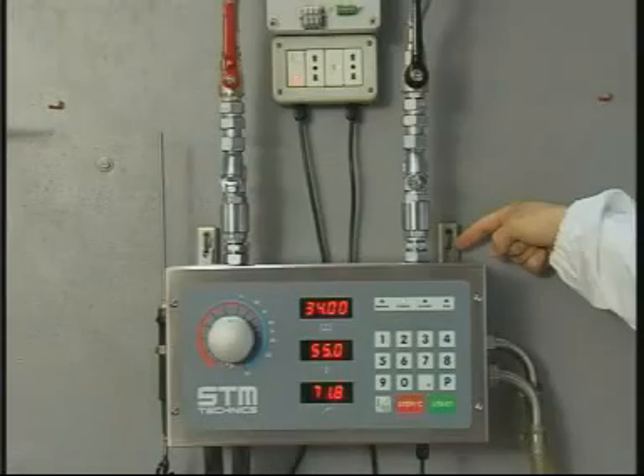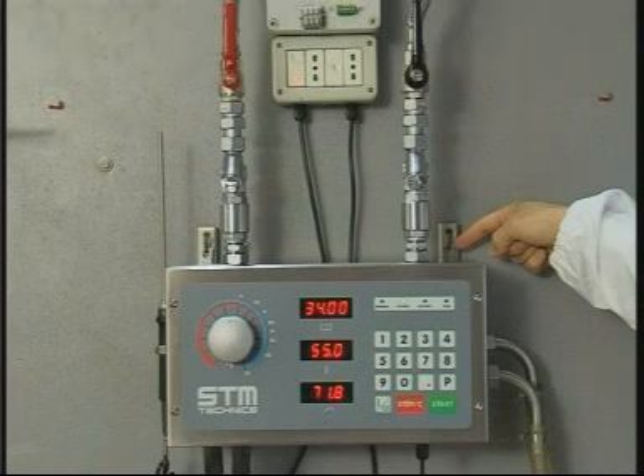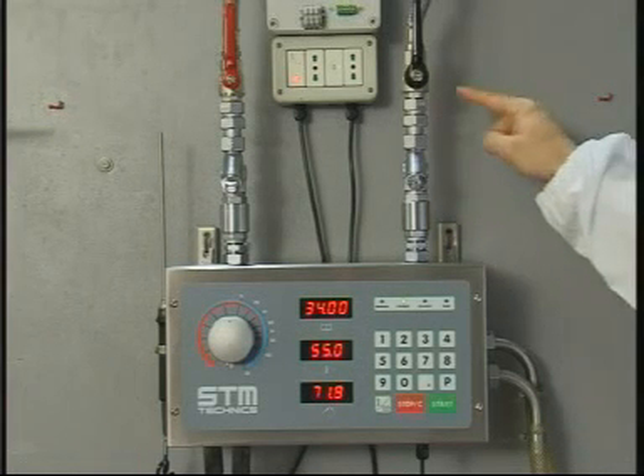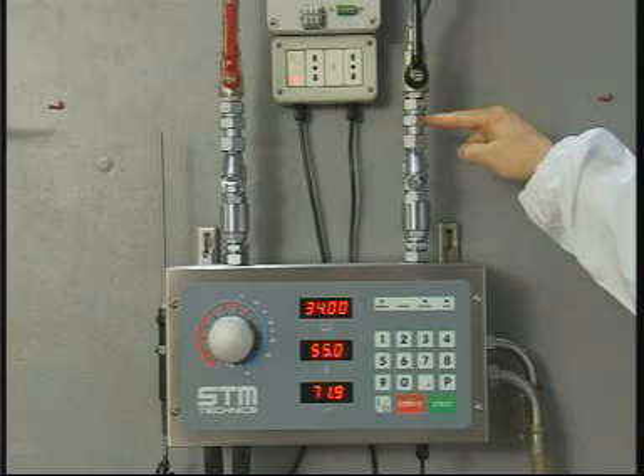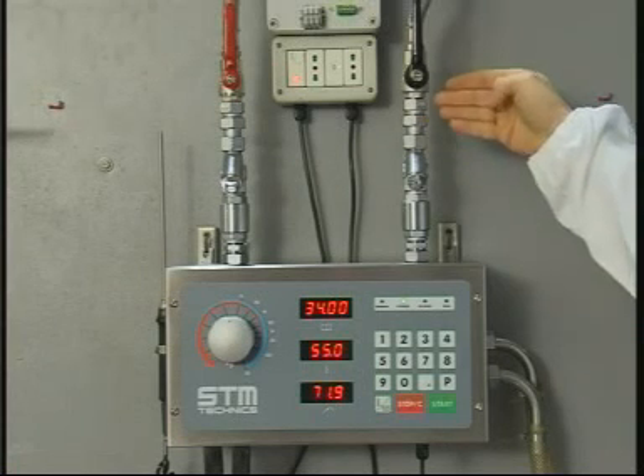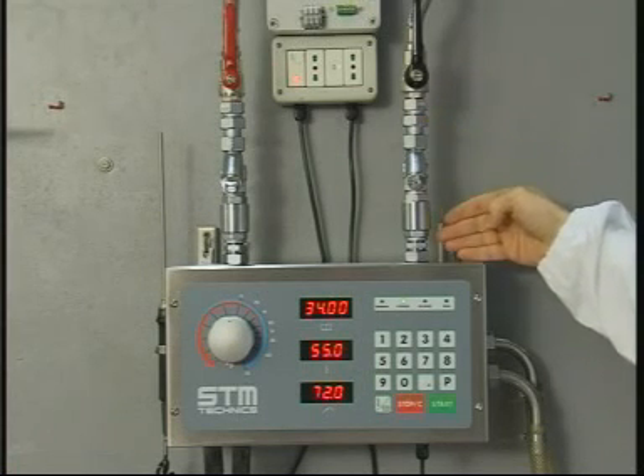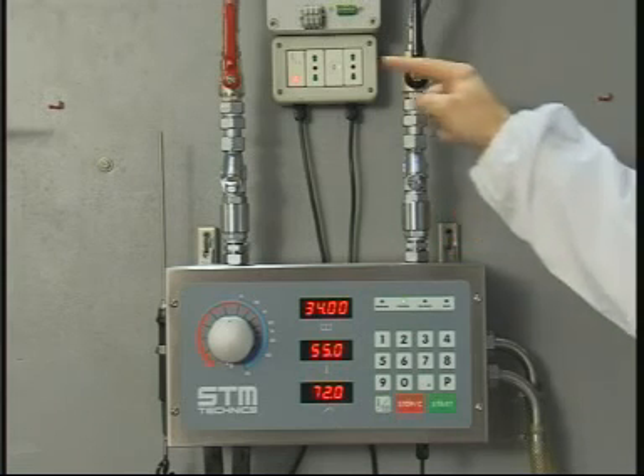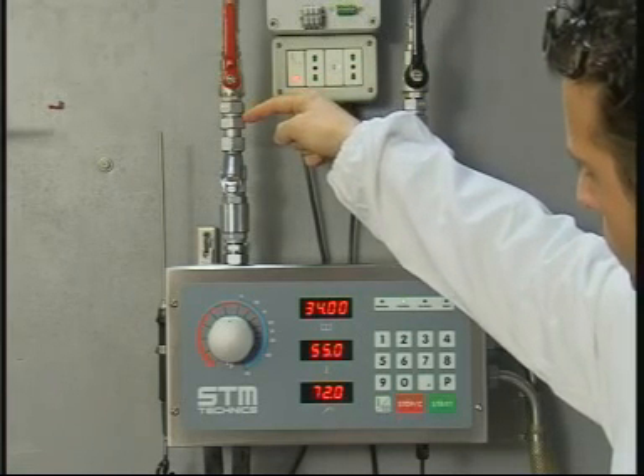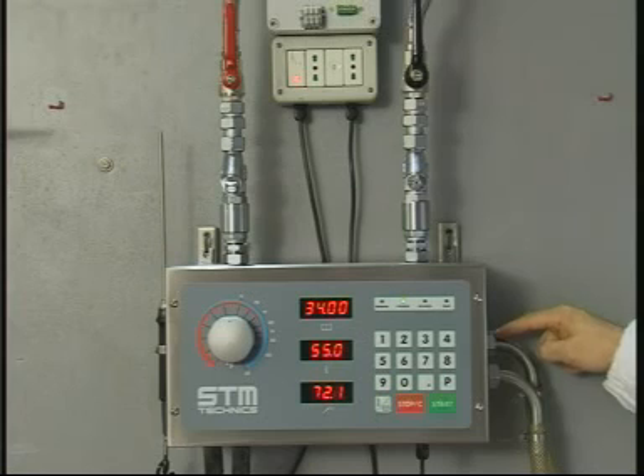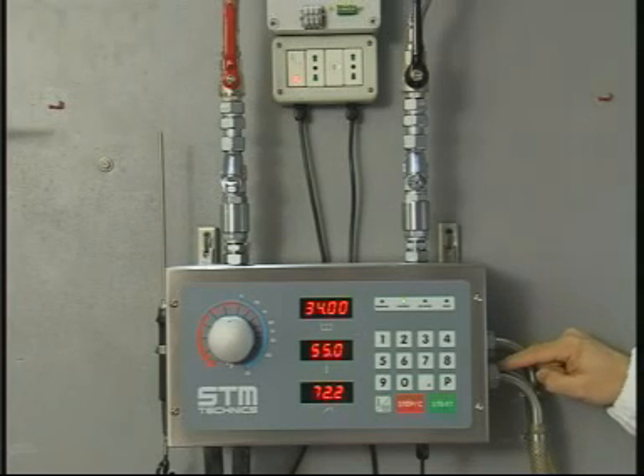Installation of the machine. Attach the machine to the wall using the 4 hangers positioned on the bottom of the box. Connect the water pipes, making sure the entrance of the colder water is always on the right, whilst that of the warmer water is always on the left. Join the discharge pipes of the bypass and the delivery outlets and tighten.